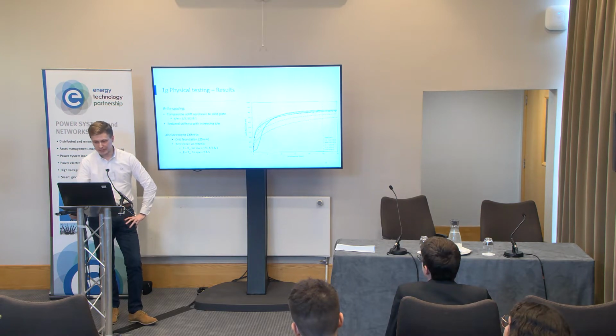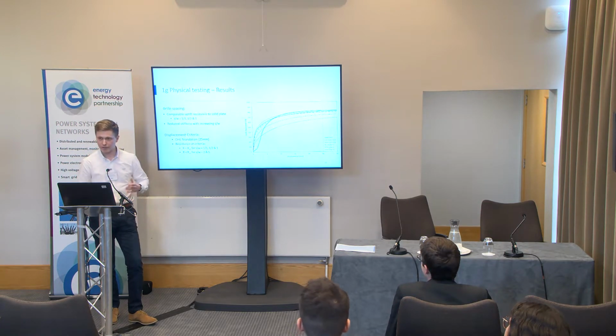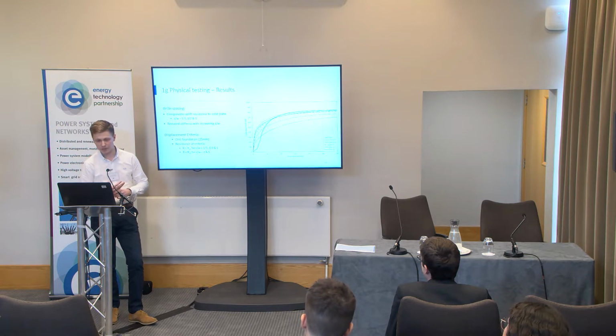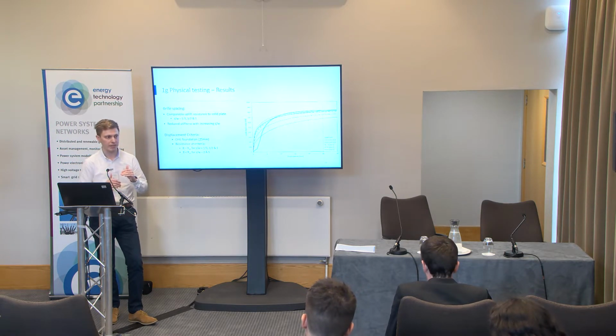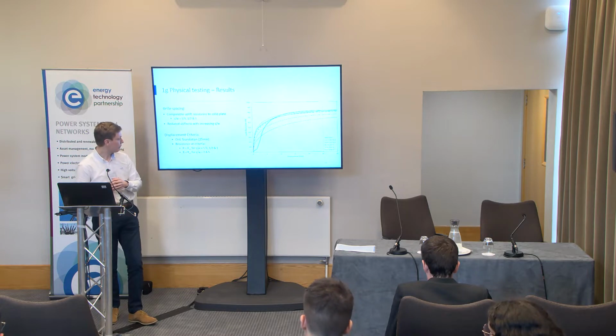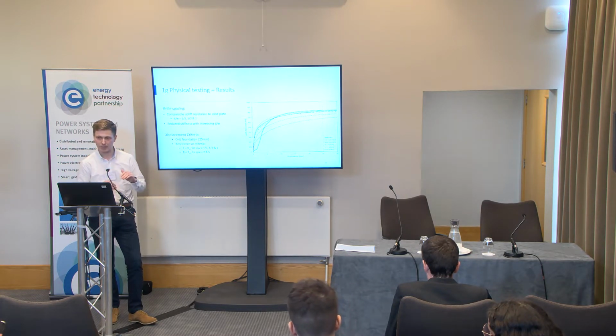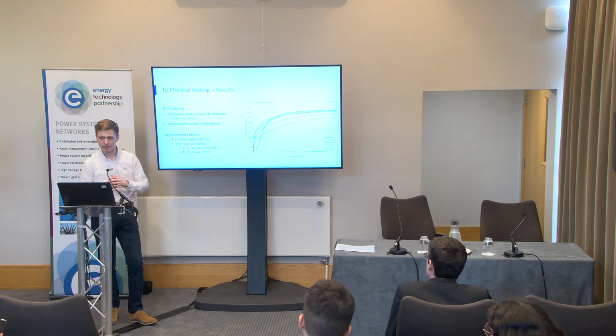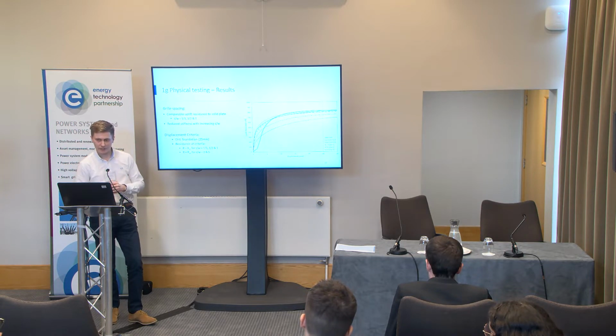This is important when considering the displacement criteria for overhead line foundations, which is a vertical displacement of 25 millimeters. As we can see, for the larger spacing ratios, we're not reaching the ultimate uplift capacity at this criteria, for those two spacing ratios at the loose relative density.